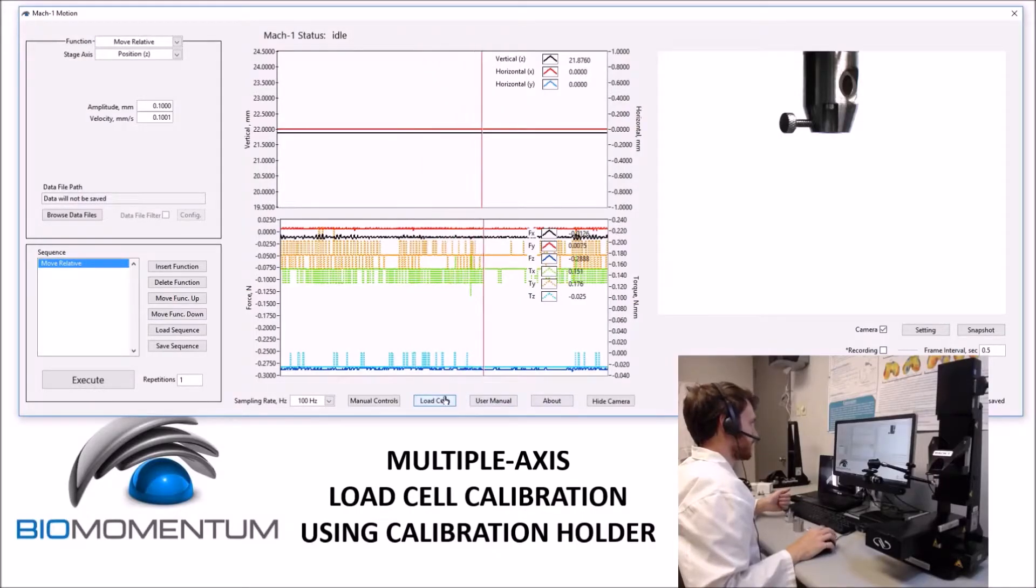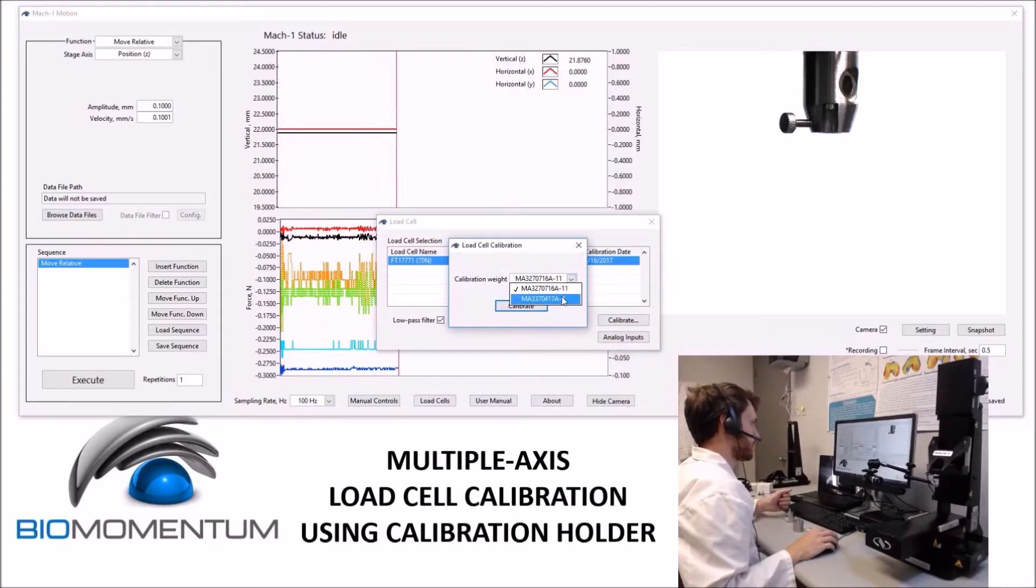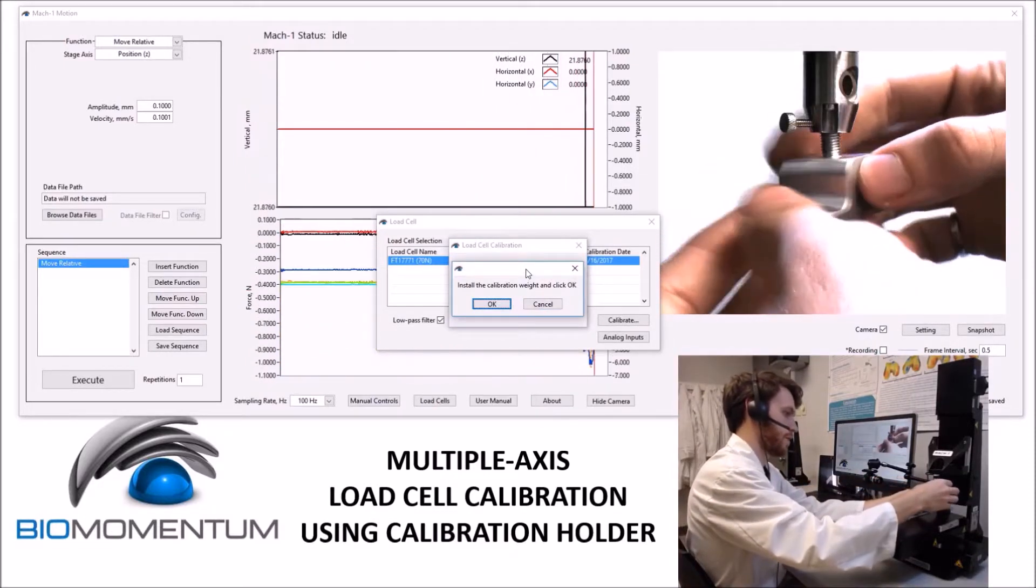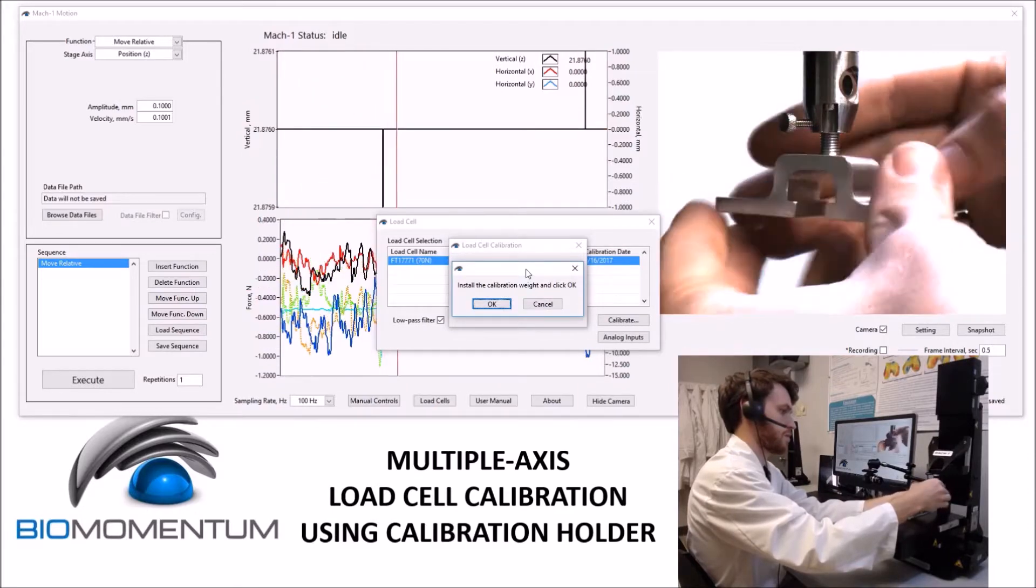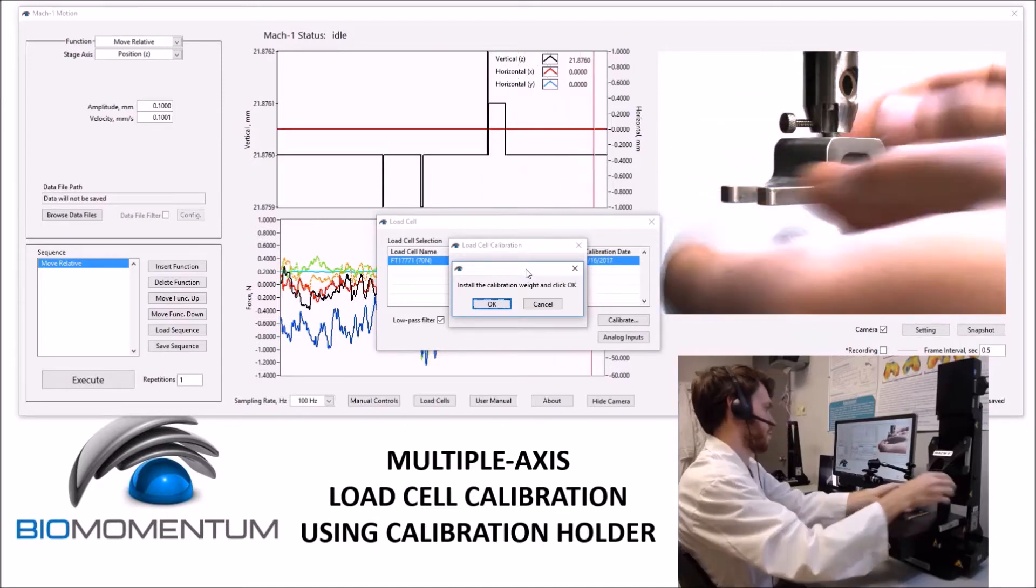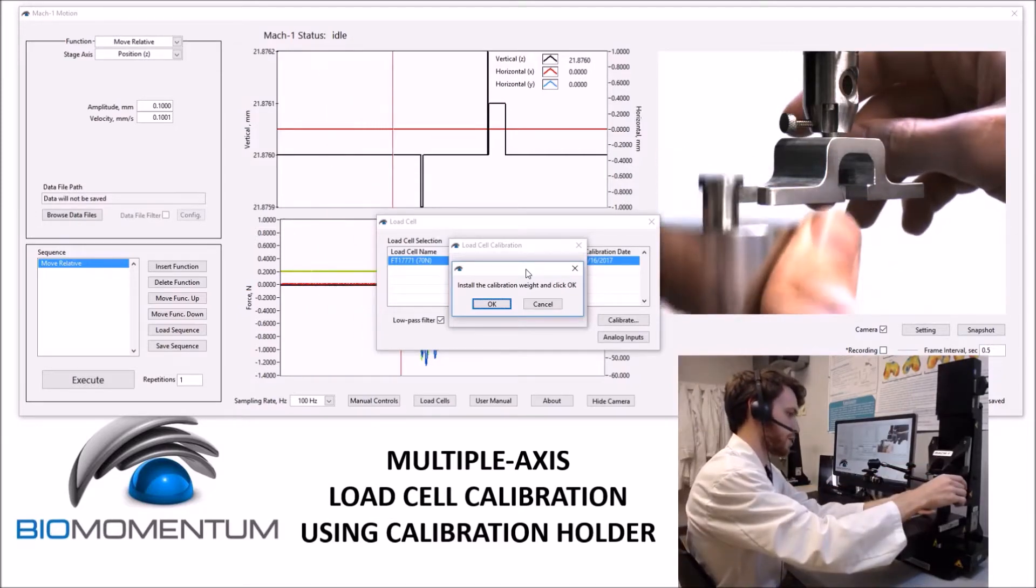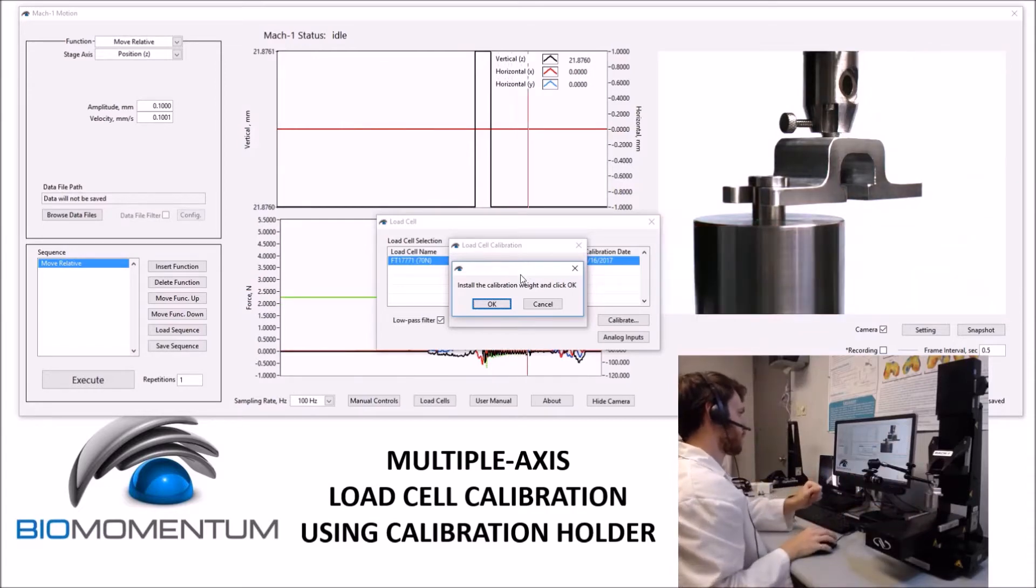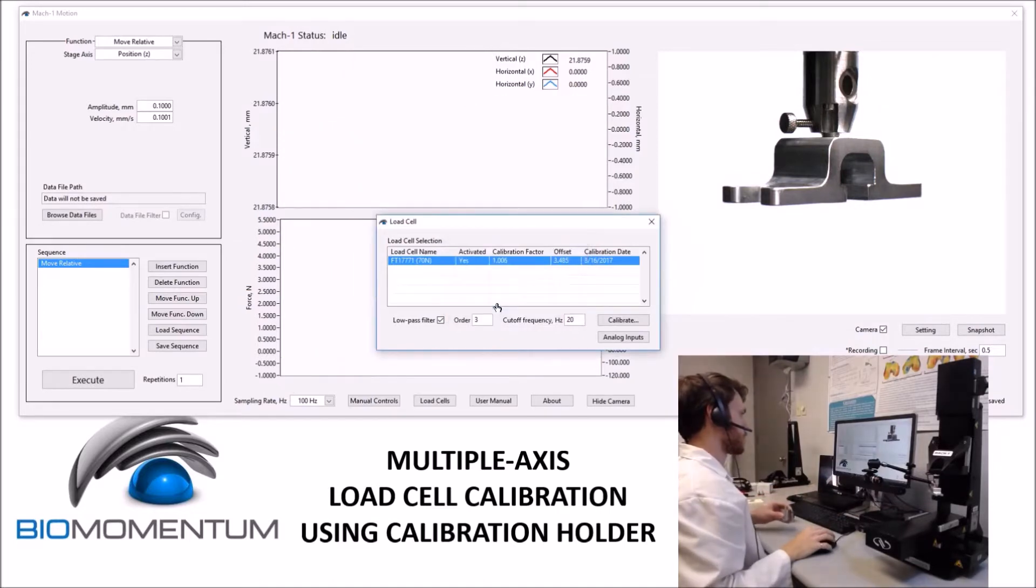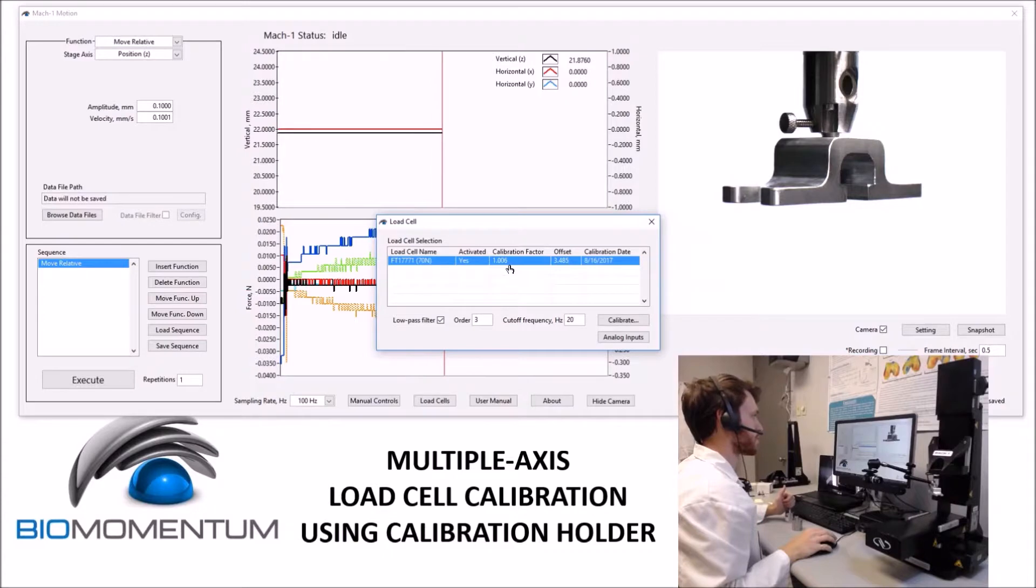To calibrate a multi-axis load cell, we'll open the load cell window, select the appropriate load cell, and then click Calibrate. To start, we'll use the calibration holder, and install this on the load cell. We will then install the calibration weight onto one of the sides of the calibration holder. Following the instructions on screen will give us a calibration factor within 5% of 1.00.